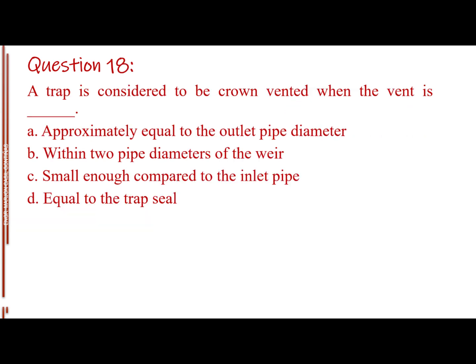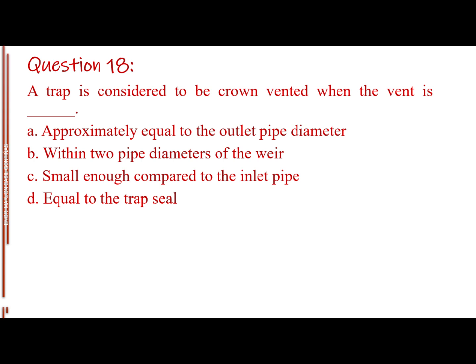Question number 18. A trap is considered to be crown vented when the vent is blank. Letter A, approximately equal to the outlet pipe diameter. Letter B, within two pipe diameters of the weir. Letter C, small enough compared to the inlet pipe. Letter D, equal to the trap seal. The answer is Letter B, within two pipe diameters of the weir.